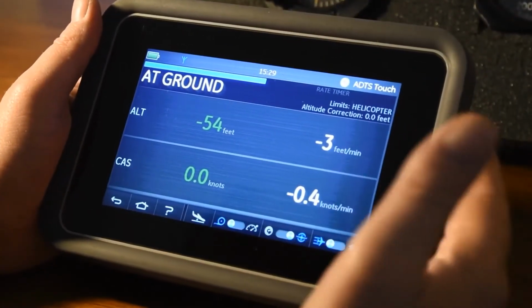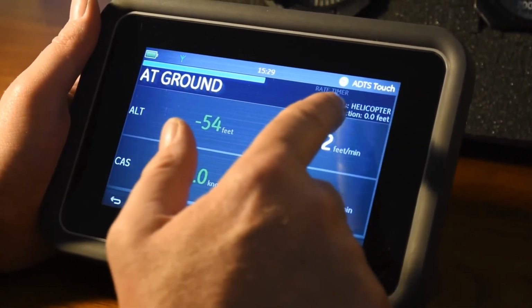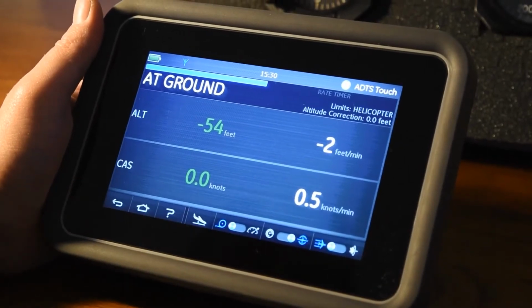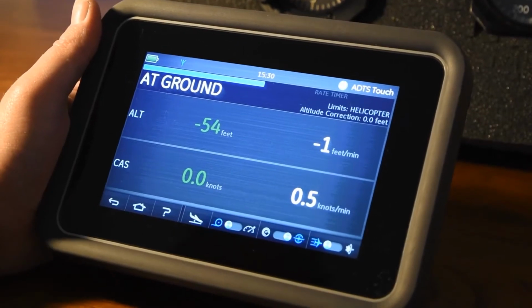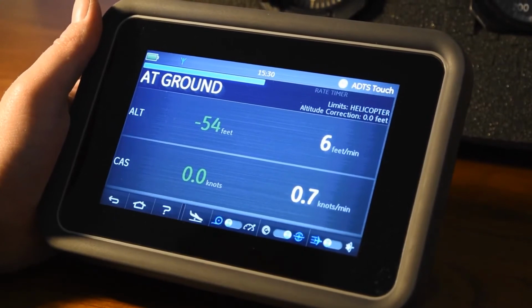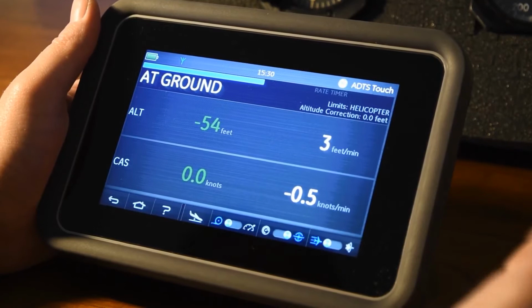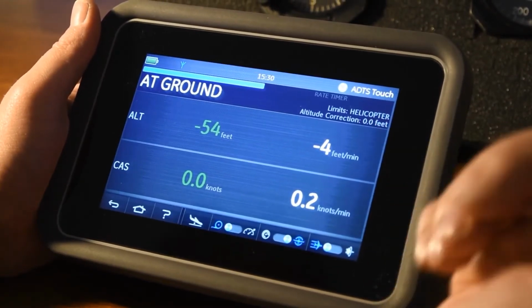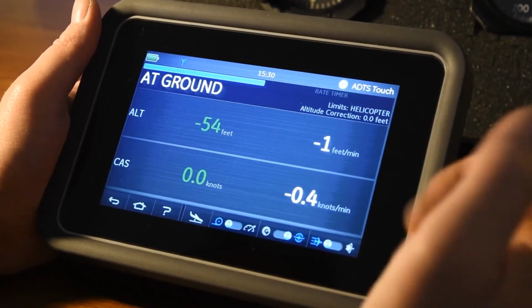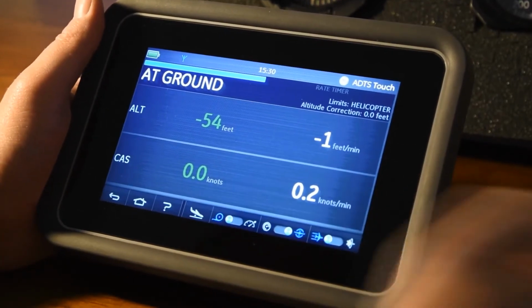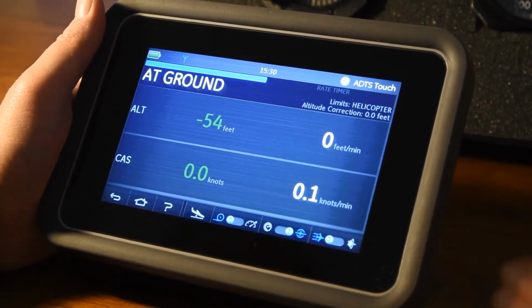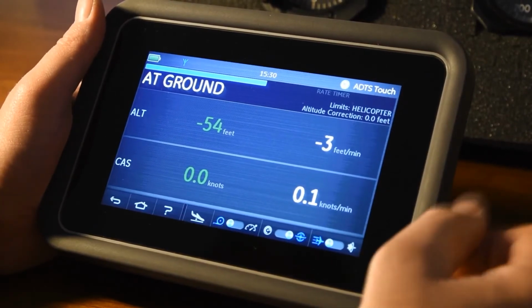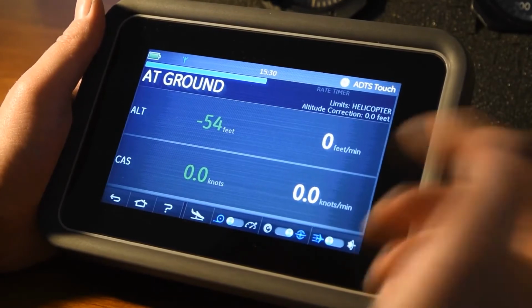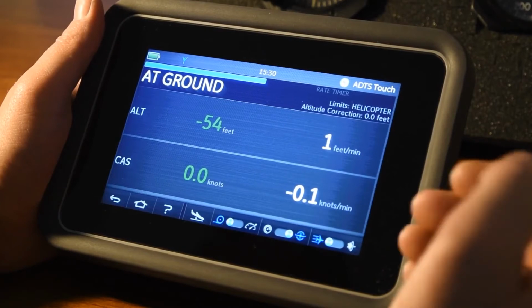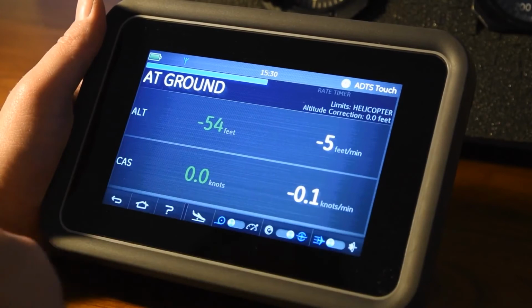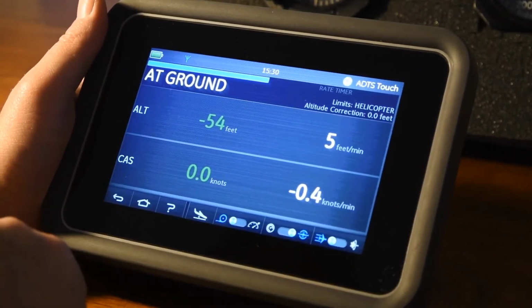Before we get started, every time the unit powers up, it will come up in what we call limits helicopter. We have limit protection, so as an operator or engineer, you do not want to enter a value that would damage any instruments on a particular aircraft. By using the limits function, you can be safe in operation and confident that you won't damage anything. The reason we start in helicopter is because that's the lowest parameters you can set for the ADTS. So if you connect to a fixed wing while in helicopter mode, you're not going to do any damage. Connect to a helicopter, you're not going to do any damage by trying to take a helicopter's altimeter to 55,000 feet, for example. It may be something you've got to remember, but you'll soon come to know that the first thing you need to do is make sure you've got the correct limits selected for the aircraft type you're working on.